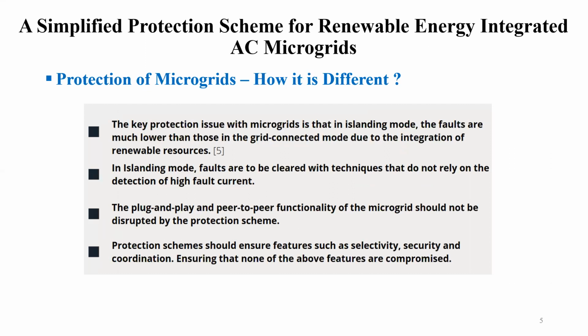So protection in microgrids, how is it different? Remember, when we are going to realize this microgrid, the key aspect is how we are going to have the protection in place. So microgrid protection is a key aspect. And again, this protection is different from the protection schemes we are using in the centralized grid. The key protection issue with microgrids is the islanded mode. Once the microgrid is working independently, that is when we have the key protection issue.